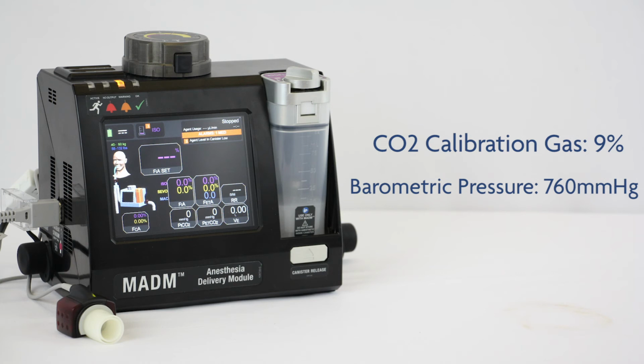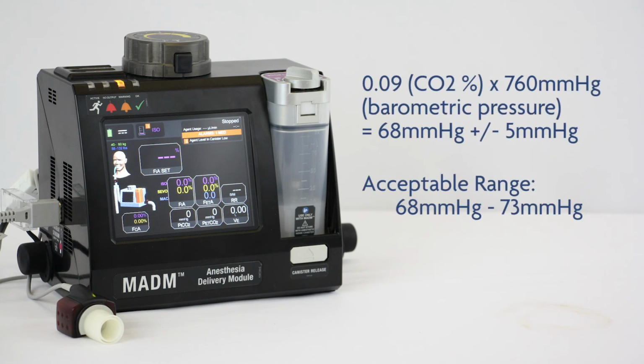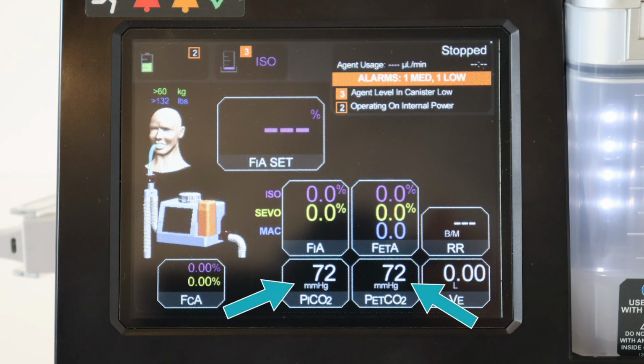Confirm the local barometric pressure. In this example, the local barometric pressure is 760 millimeters of mercury. Convert the CO2 concentration to millimeters of mercury by multiplying the percent concentration by the local barometric pressure. In this case, we've multiplied 0.09 by 760 millimeters of mercury, indicating that when we apply the calibration gas, MADM should display 68 millimeters of mercury, plus or minus a tolerance of 5 millimeters of mercury. When we apply the calibration gas, we see a value within the acceptable range.